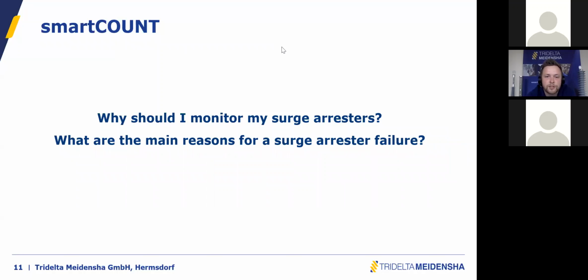The very first important question: why should I monitor my surge arresters? Like Florent said before, maybe the monitor is almost as expensive as the surge arrester. I could just get a replacement surge arrester in exchange in the moment the surge arrester is defective. Yes, so why should I monitor surge arresters? One important question. And the second, if I monitor surge arresters, what are the main reasons for a surge arrester failure, and how can I detect them?